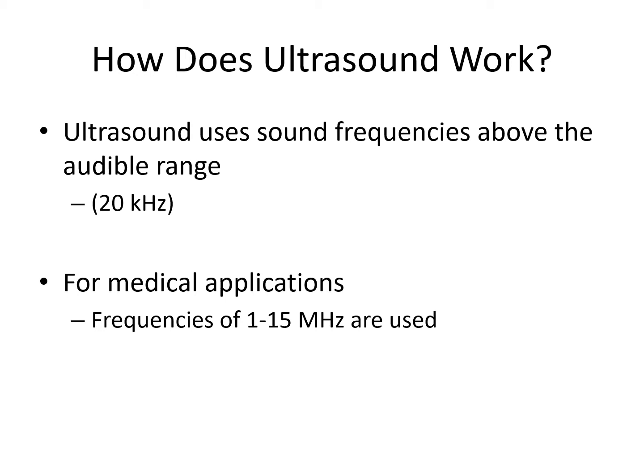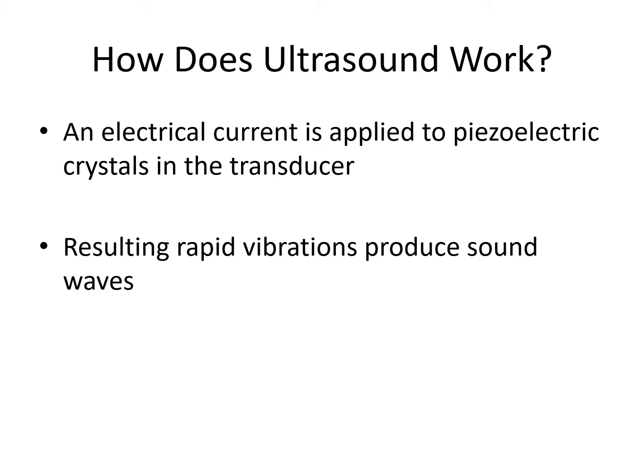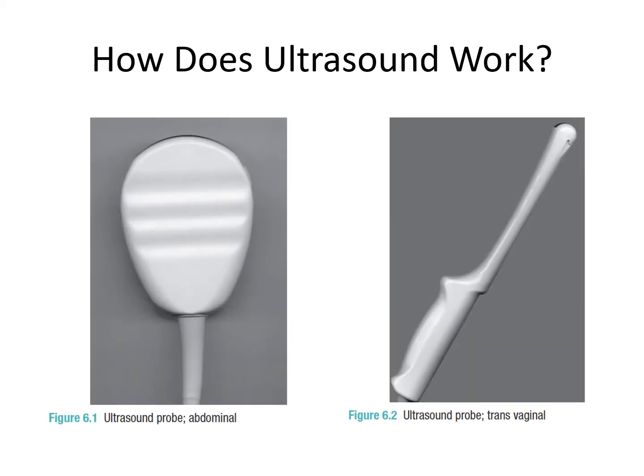First let's discuss how ultrasound works. Ultrasound uses sound frequencies which are above the audible range, hence the term ultrasound. The audible range tends to be up to 20 kilohertz, and for medical applications we're using much faster sound waves in the region of 1 to 15 megahertz, or millions of Hertz. These sound waves are created through application of electricity to ultrasound transducers or probes, which contain piezoelectric crystals, resulting in very rapid vibrations which produce the ultrasound waves.